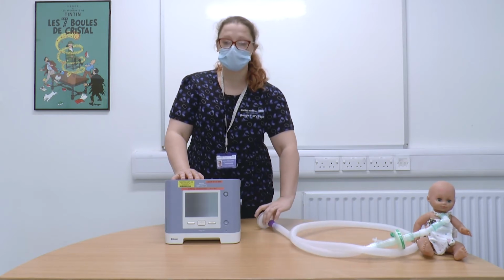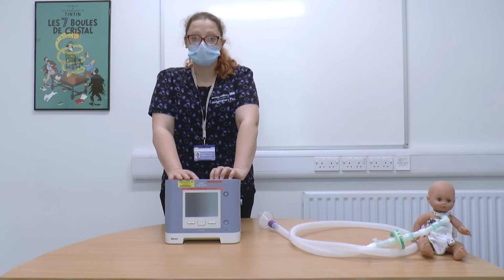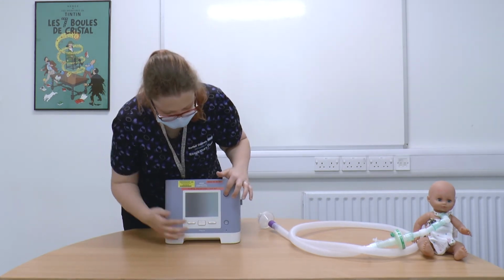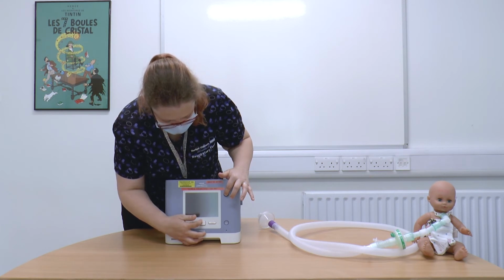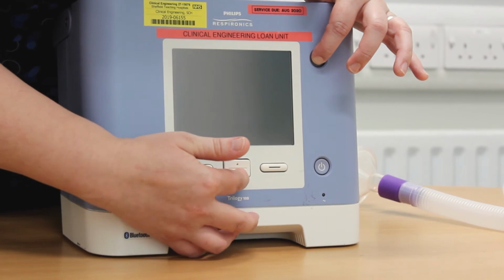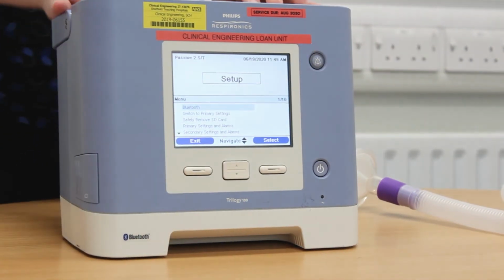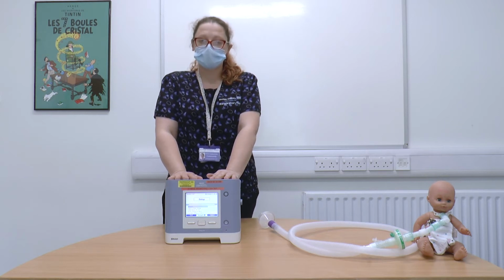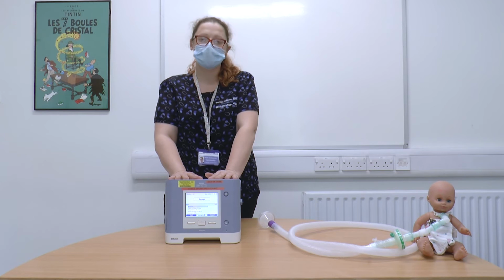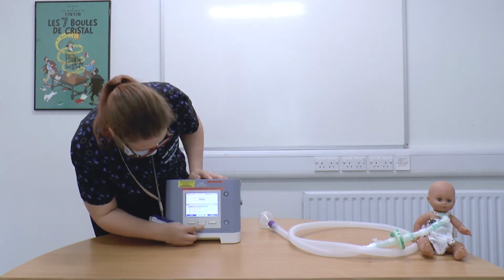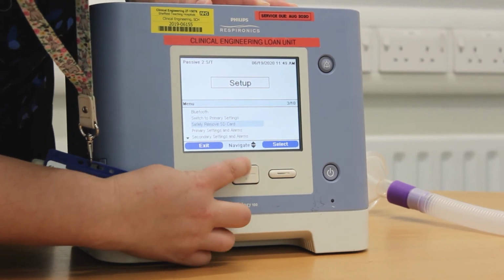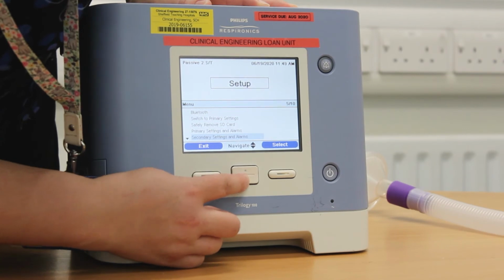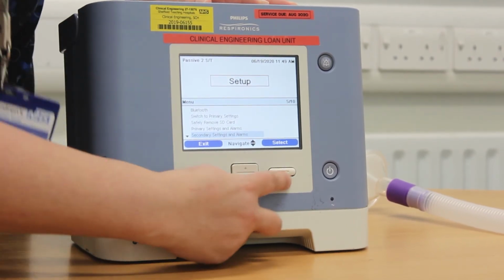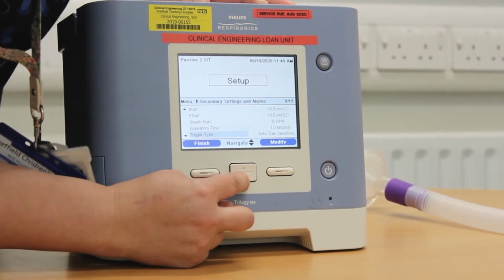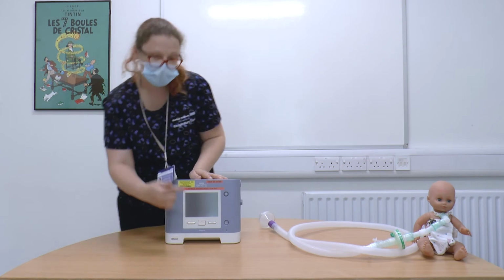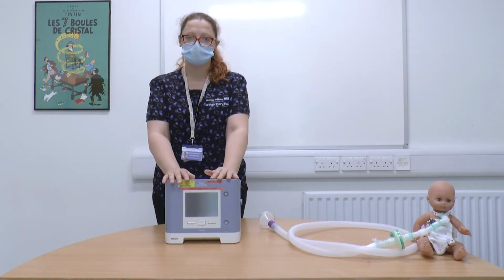If you want to turn the ventilator on not attached to the child, in order to look through the settings, you can hold the silence button and the arrow, and after about 5 seconds it will turn on in what we call training mode. When you have turned it on in training mode, that is when you could make clinical changes, so this should not be done unless you are the Embrace team or one of the staff changing settings. But it does allow you to go between looking at primary settings and alarms. I scroll down and press select, and I can see the different things happening. Or I can finish everything and it will automatically turn off and go back to a black screen.